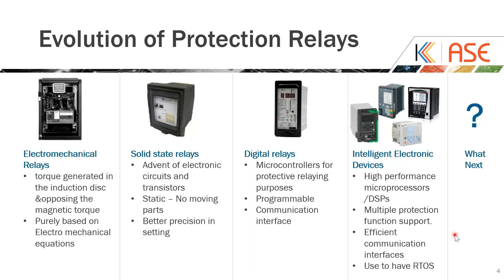Virtual protection relay is basically an approach to decouple relay software from the dedicated hardware, leveraging the IEC 61850 standard and advanced virtualization technology. We'll call it VPR from now onwards. VPR will ensure meeting all the existing characteristics of a relay, but with greater flexibility, portability, resilience, and interoperability. That will be the aim of the VPR.